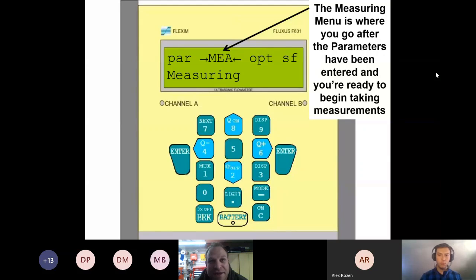We see that a lot on brand new chilled water installations where they haven't removed the air out yet. And a way to diagnose that is if they could stop the flow of the water and let the pipe settle, and we have good full pipe, good sound speed. And then when the pumps are turned back on and you see that ramping, that just shows you that there's actually air in the pipe. So it's a good tool in that regard for diagnosing different problems.